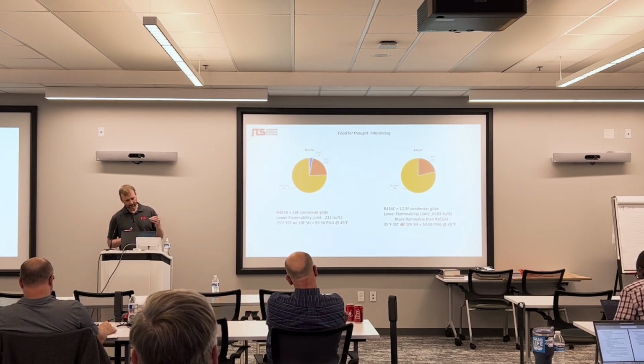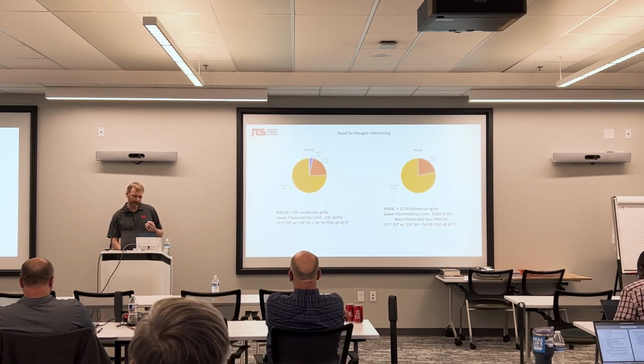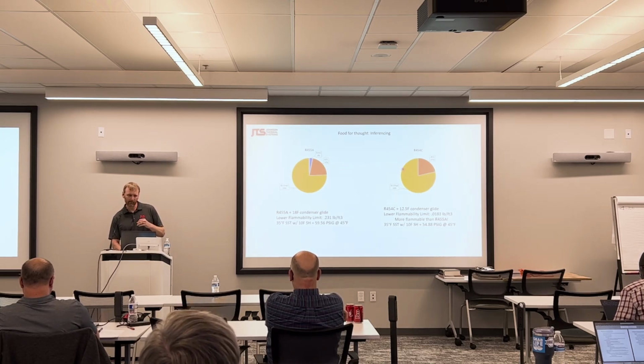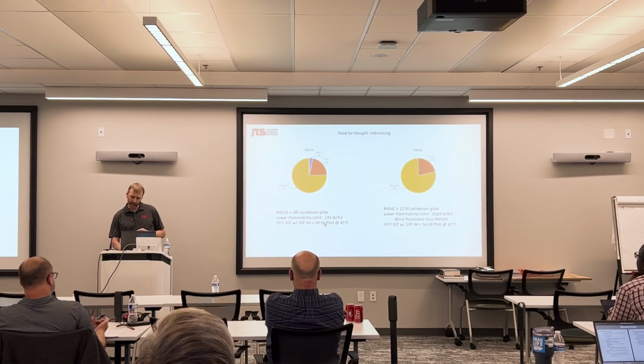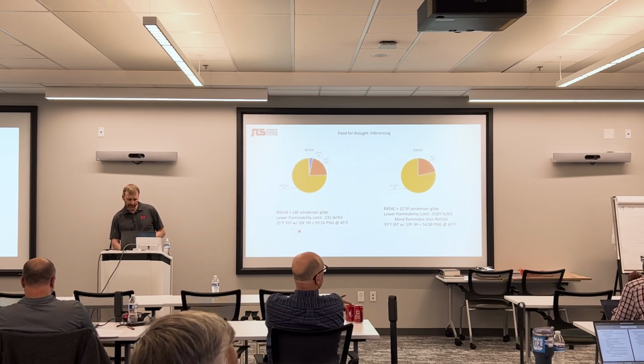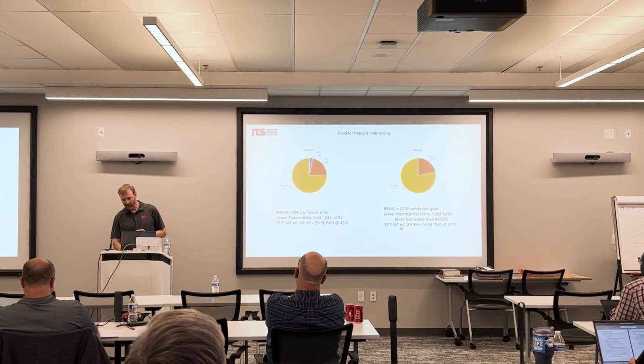So if you're designing it, it's kind of a scary thought. If you design a system around the lower flammability limit for this less flammable refrigerant, but after so many leaks that refrigerant is probably going to become more and more flammable. Another thing that you'll notice is our saturated suction pressures. Our pressures are going to be a little bit lower. So if we look at a 35 degree suction temp, 10 degrees of superheat with R455A, that's 59.56 psi. With R454C, the equivalent pressure is about 55 psi.